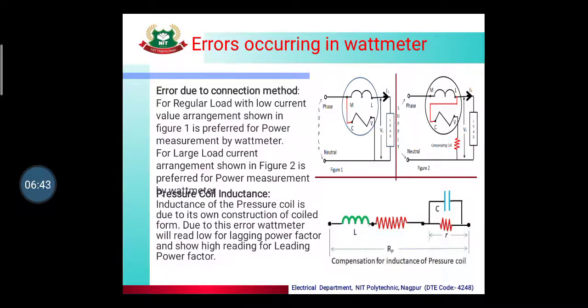Now let's look at errors in the watt meter. The first error is due to the connection method — depending on whether the load current is small or large, you choose the appropriate connection figure. The second error is pressure coil inductance, which arises due to the coil's own construction. Because of this error, the watt meter will read low for lagging power factor and show a high reading for leading power factor.